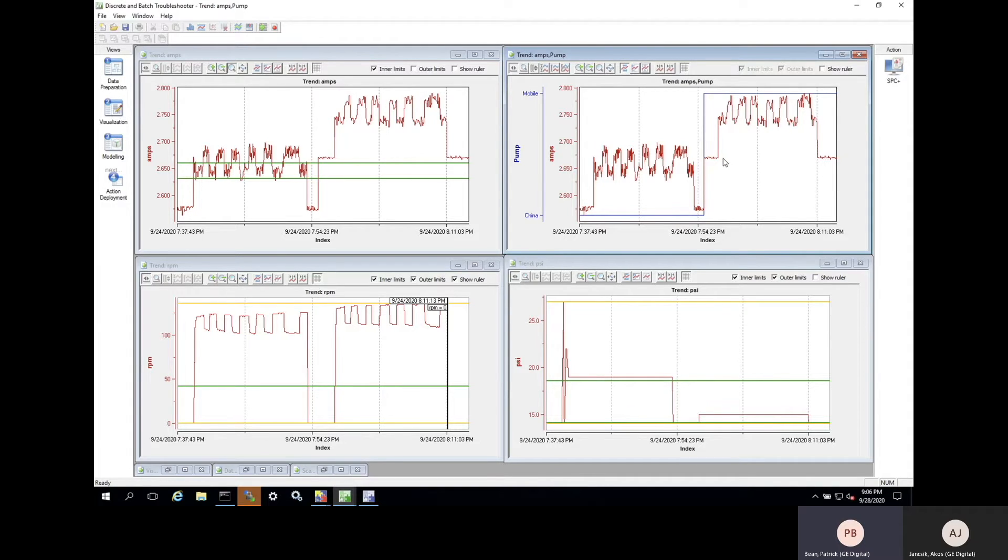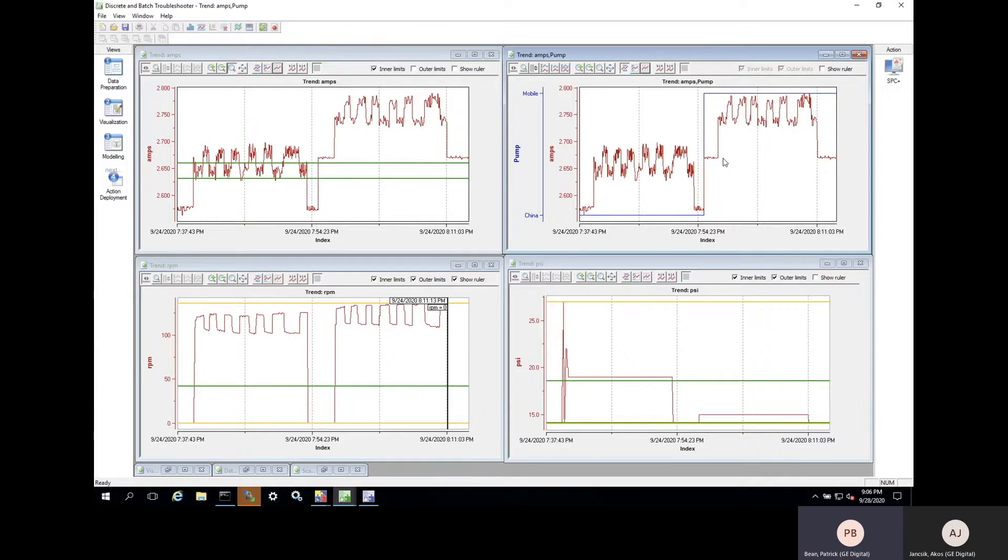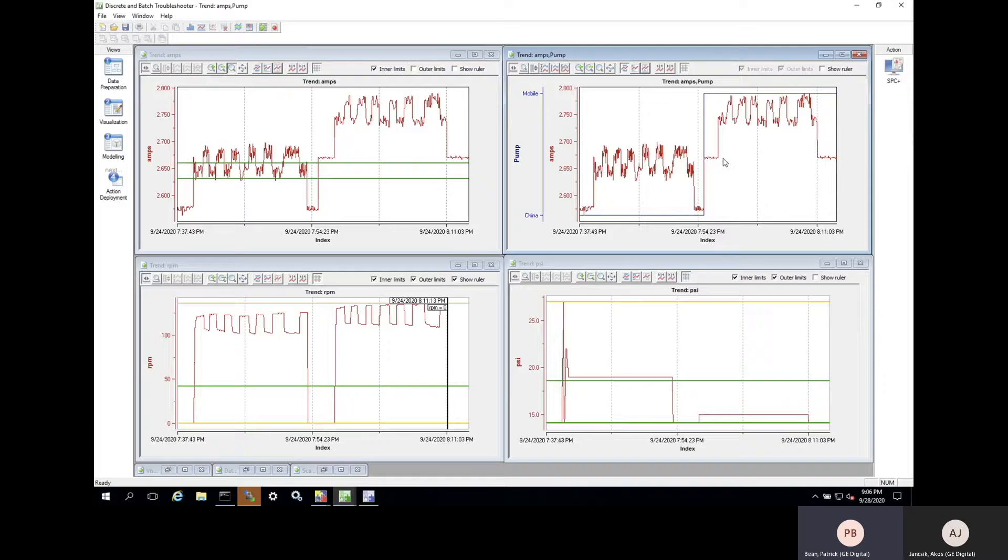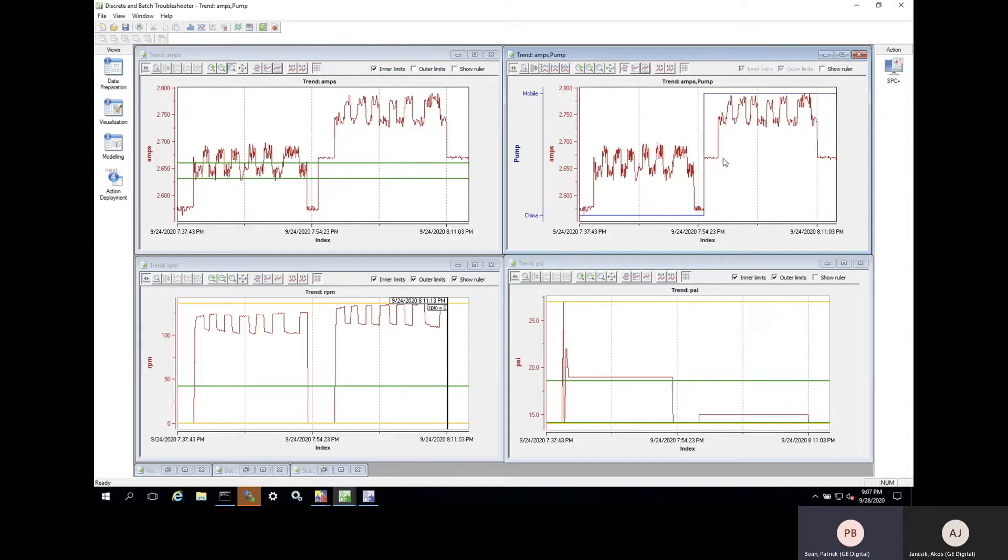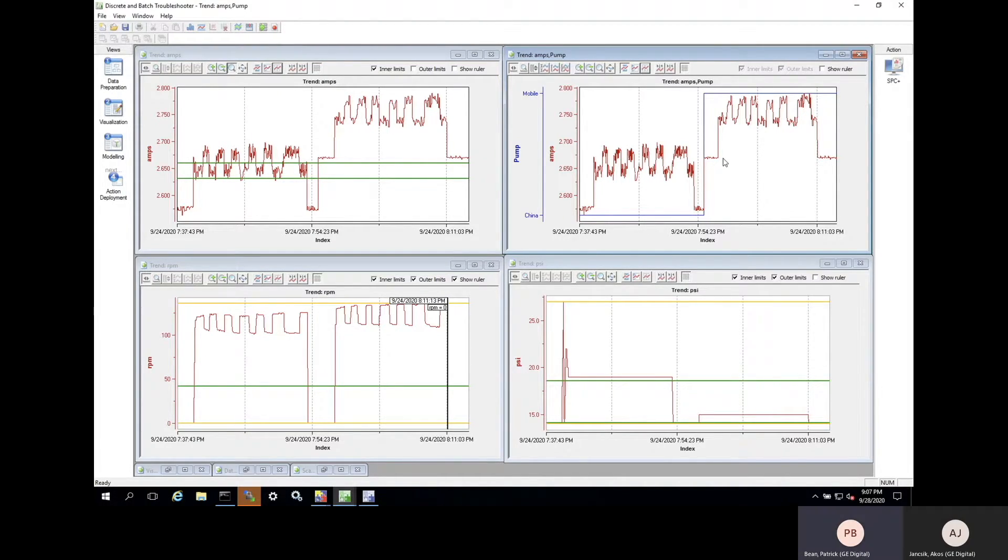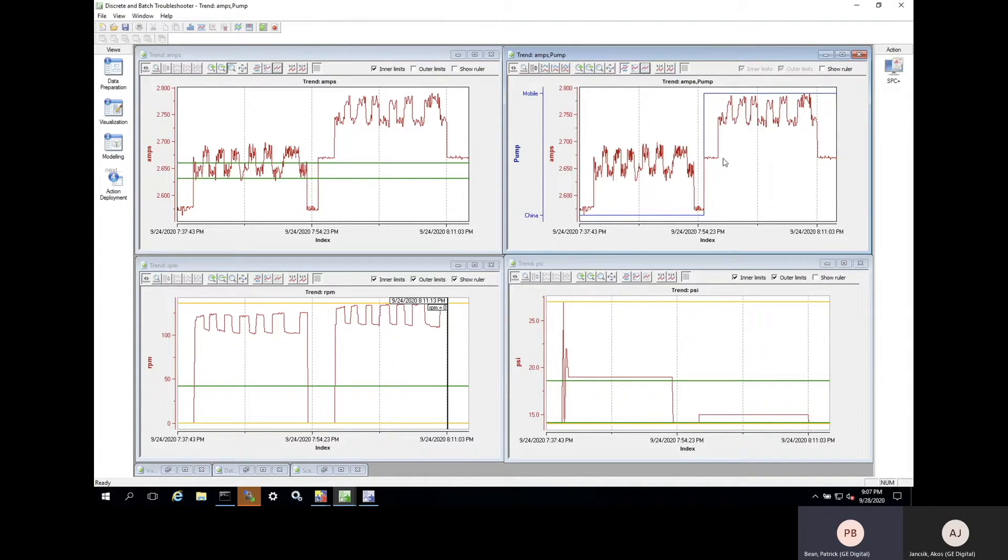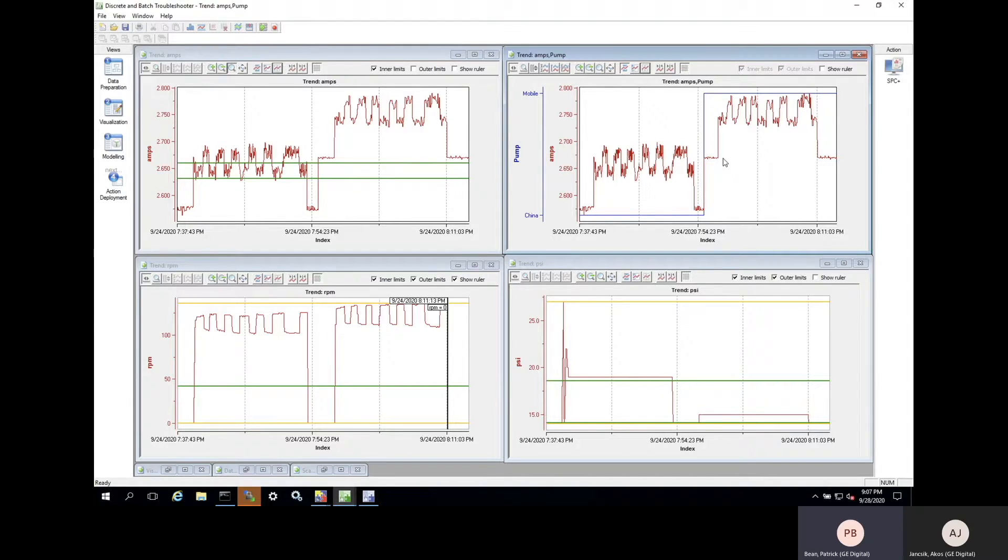It turns out that several factors, such as equipment age, operating environment, maintenance practices, ambient temperature, and more, all determine a pump's baseline for what normal looks like. Furthermore, that baseline moves around with age and with each season. So clearly, our plan to implement a simple, limit-based analytic across all 250 pumps isn't going to be feasible. So, we'll use machine learning instead.